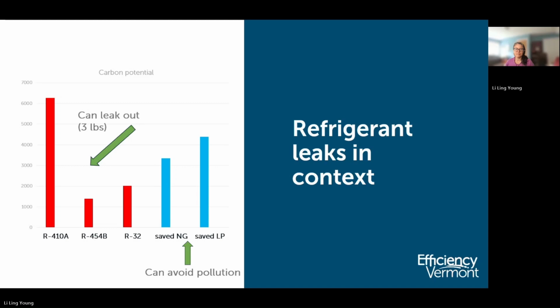The blue bars add up every year. That means every year you can not burn the fossil fuel that the heat pump is displacing. And of course, that's what's so great about heat pumps. They really do save carbon. But those red bars can erode the benefits if the refrigerant leaks out. And sometimes those red bars add up too if there's a refrigerant leak and it's not repaired and the system keeps getting refilled with refrigerant. But those red bars don't have to erode the benefits of the blue bars. As long as the system doesn't leak and the refrigerant is recovered at the end of life, you get all the benefits of years of blue bars and none of the downside of the red bars.